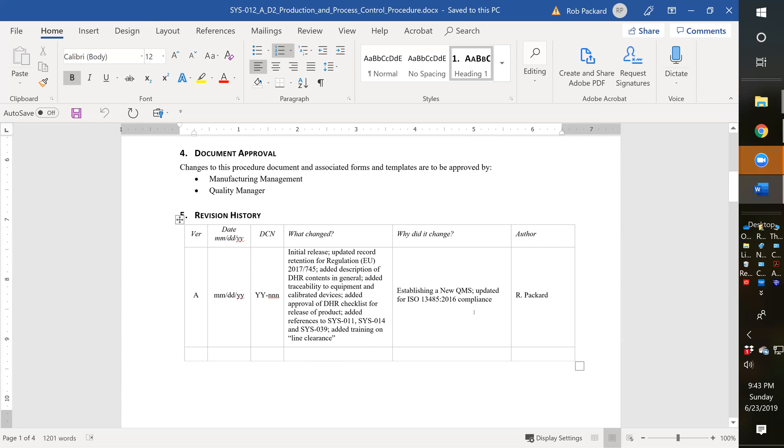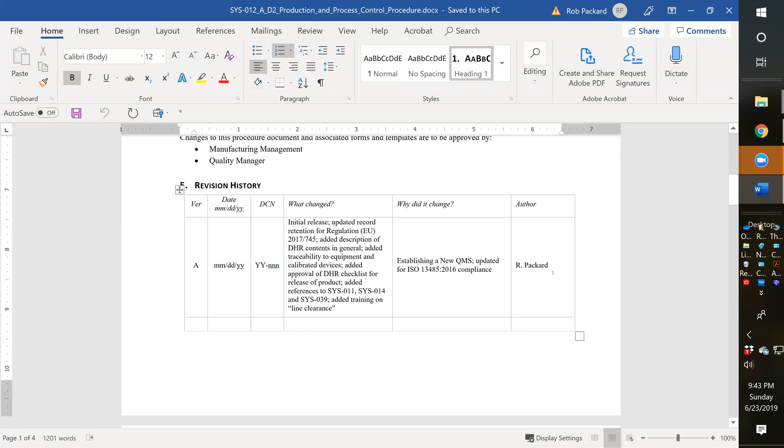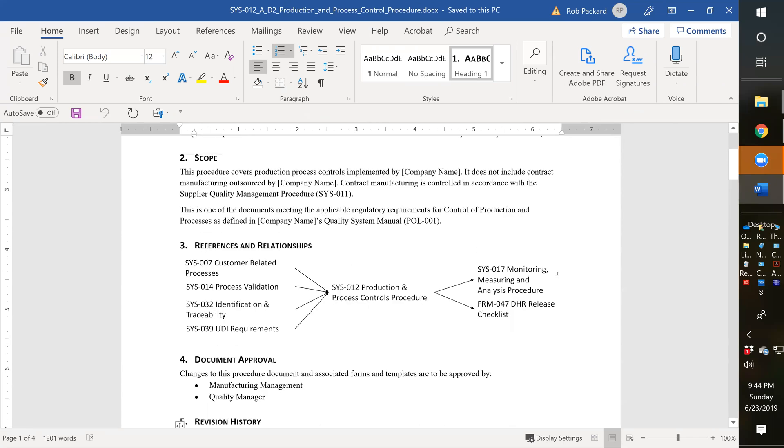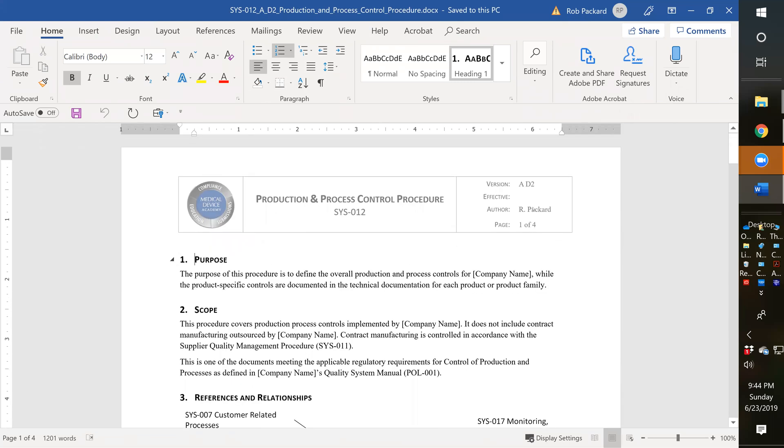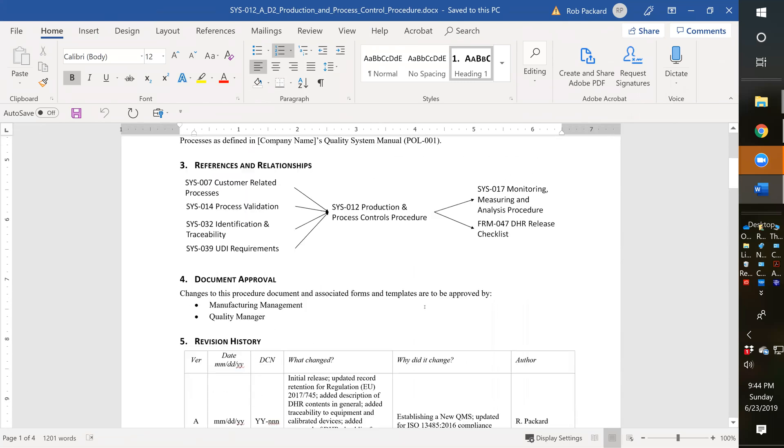It's compliant with ISO 13485:2016. When you release the procedure, you're going to indicate the date you release it, the document change notice or DCN that you're releasing it on - this is just a year plus a sequential number. You can put your name here instead as the author, just like you would up here.